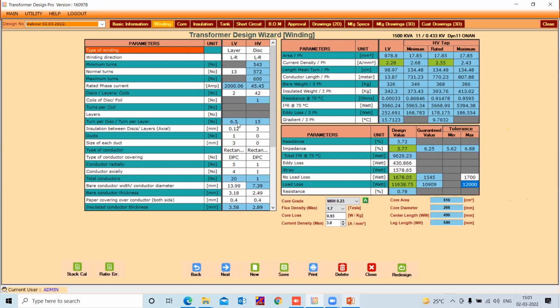Then you can also see below that turns per disc or the layer, the insulation between them, number of ducts, the size of duct, the total number of conductors, the type of conductor, the conductor covering type. You can read here, it is mentioned as double paper covering. You also have the option of triple paper covering. You can also go for super enameled. All these options are there for both LV as well as HV winding.